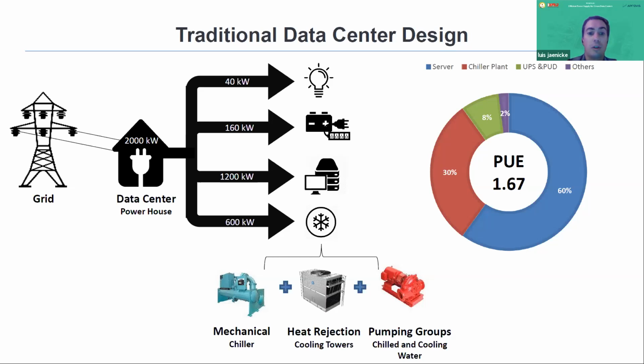So 600 kilowatts of this data center consumption is actually going to the chiller plant. Chiller plant essentially consists of the mechanical chiller, heat rejection equipment like a cooling tower, and then some pumping groups like chill water pumps and cooling water pumps. But the majority of the consumption is concentrated in the mechanical chiller, in the compressors. And if we see in percentage, roughly around 30% of the total data center consumption is going to the chiller plant. So therefore, for 1.2 megawatt IT load, I will need to import 2 megawatts of power from the grid, okay?